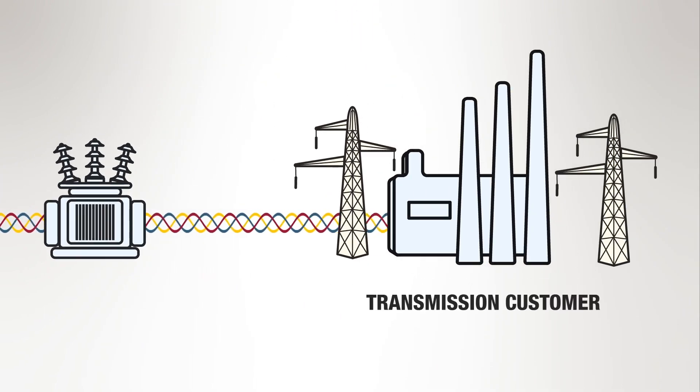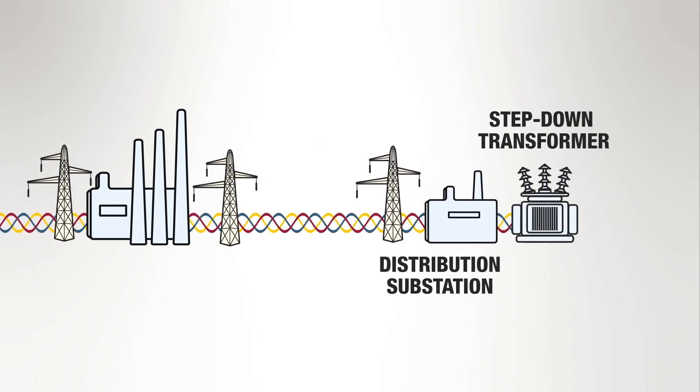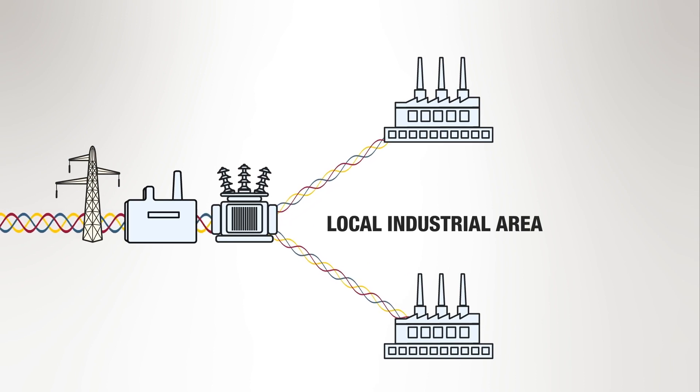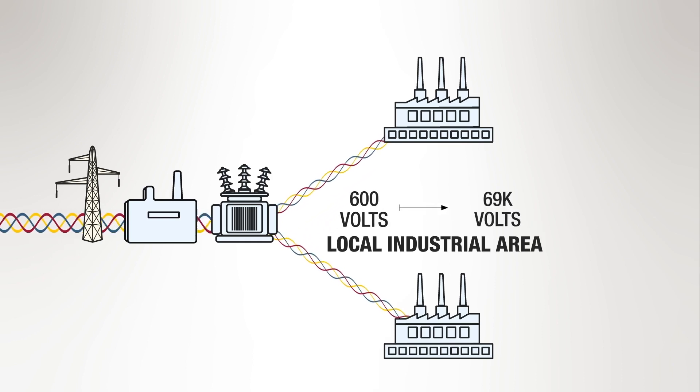The transmission customer then receives the power at the higher voltage. Very few end customers require this high voltage or have the equipment to handle it. When the power exits the transmission customer, it will enter a distribution substation where a step-down transformer reduces the voltage for use in a local industrial area. This medium voltage power is used by industrial customers such as factories and other large users. Medium voltage customers use power ranging from 600 volts to 69,000 volts or 69 kV.